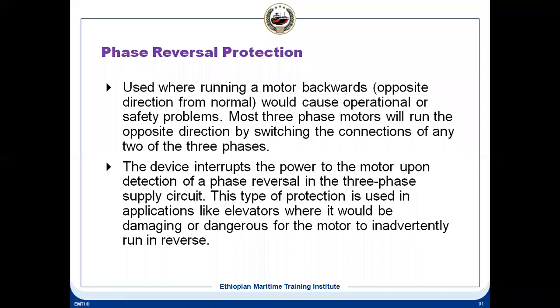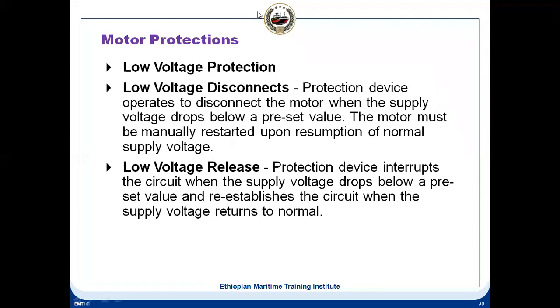Phase reversal protection. As I told you, it is not mandatory to have all these protections, but you will find it in some starters. Now, where do we need phase reversal protection? It is required for things like elevators or cranes, which you don't want to rotate in the reverse direction. It is used wherever running a motor backwards would cause operational or safety problems. Most three-phase motors will run in the opposite direction by switching the connections of any two phases. But this device will interrupt the power to the motor upon detection of phase reversal in a three-phase supply circuit. This type of protection is used in applications like elevators, where it can be damaging or dangerous if the motor runs in the reverse direction.